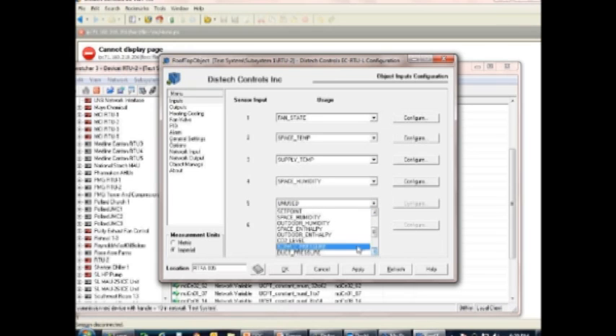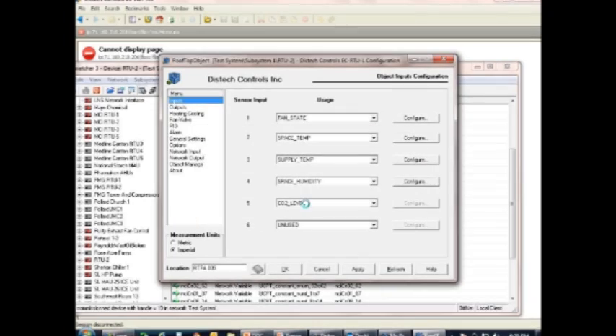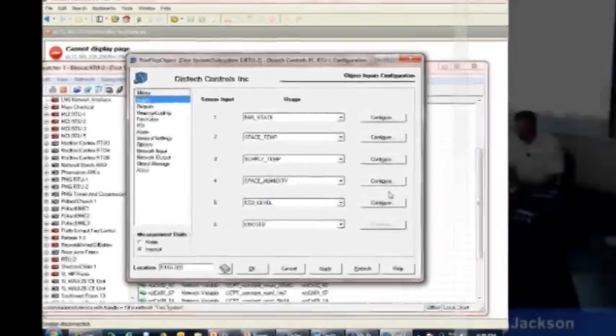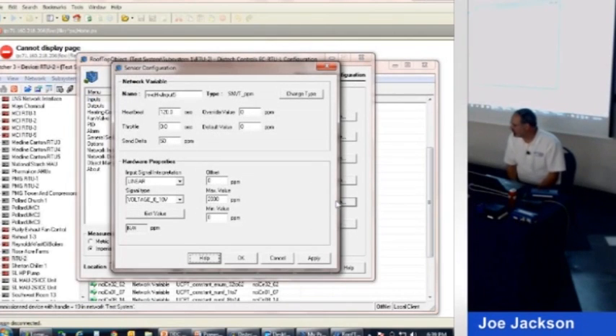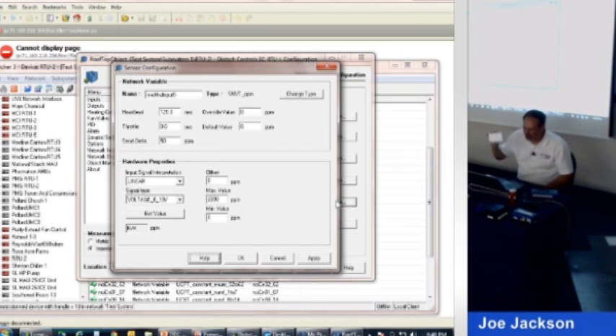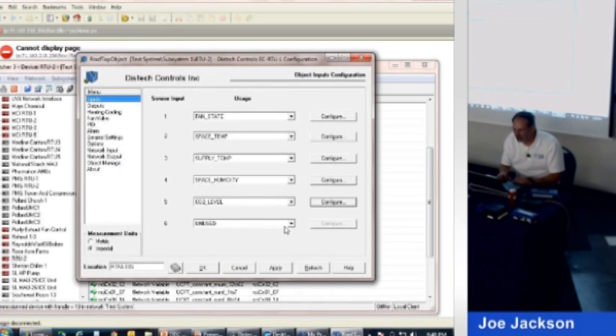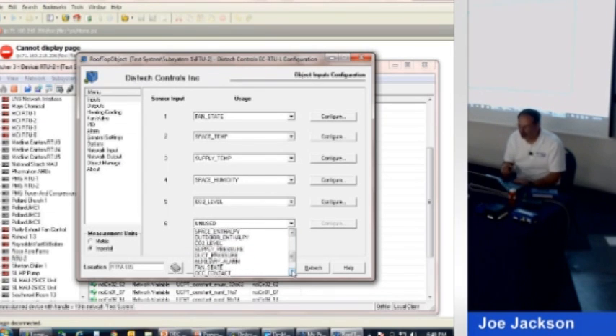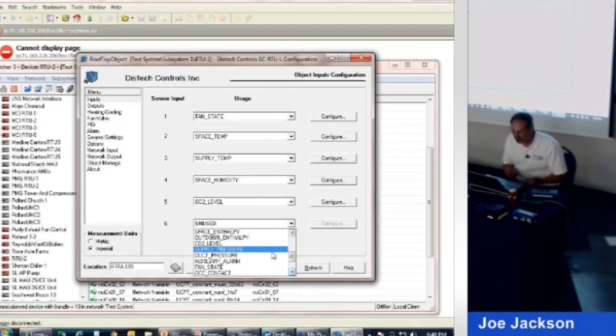CO2 levels. Be a good thing to have on a rooftop today. Again, we can let it do its own thing, but a standard CO2 sensor, at least the ones we sell, are 0 to 2,000 parts per million. Most of the time in a classroom or something, you want to keep it down around 1,000 parts per million, so right in the middle of the range. These rooftop controllers have 6 inputs, so we could throw one last thing on here. See what else there is. If you wanted to watch the duct pressure, you could. If it was just a standard constant volume rooftop, we probably wouldn't do that.